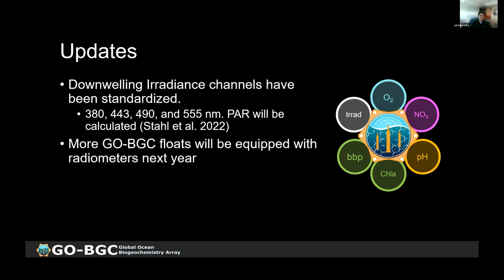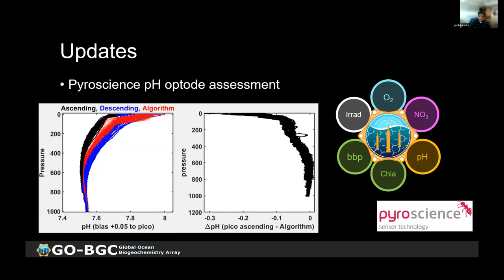There is growing interest in alternative pH sensors. We are exploring the PyroScience pH optode. Using underwater gliders, the standard foils show that the sensor response time is slow, leading to large hysteresis between descending and ascending profiles. We are working with PyroScience to test a faster response foil, and hope to have several floats with this updated foil deployed in the next couple of months.